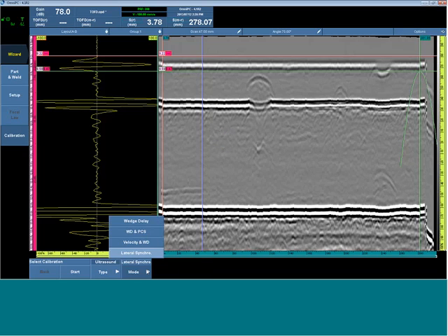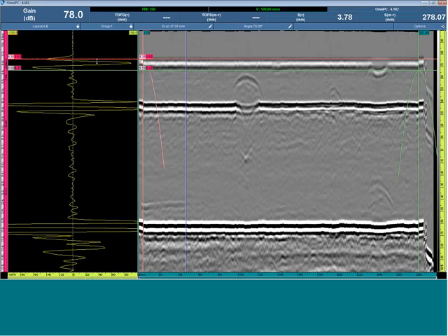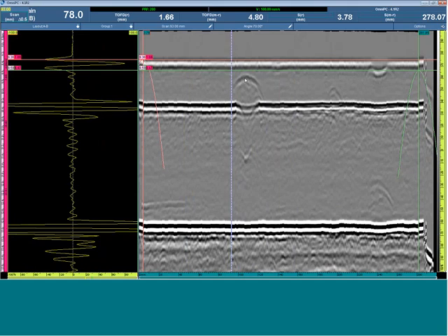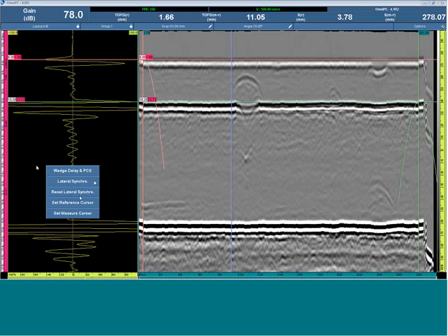On any flaw, set reference cursor, set measure cursor, drag data cursor, and zoom. All those functions previously required touch screen mode manipulation and several extra button clicks or touchscreen manipulation than was necessary. Now it's made much faster and easier.